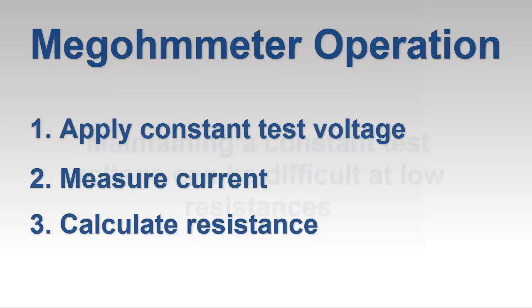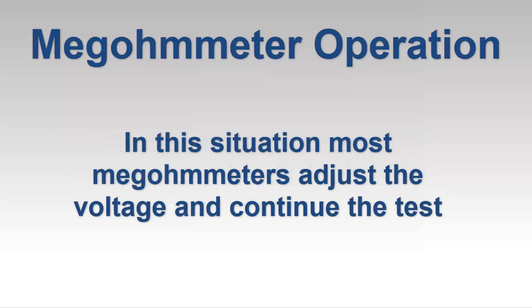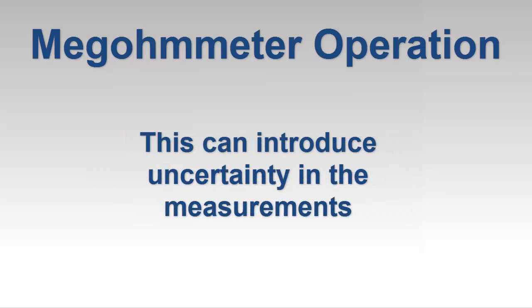Unfortunately, holding the voltage constant can be a challenge at lower resistances. To accommodate this, most megohmmeters lower the voltage level in this situation and continue with the test. This may introduce a level of uncertainty into the data, since ideally all measurements within a test should be made at the same test voltage to ensure a true comparison amongst the readings.